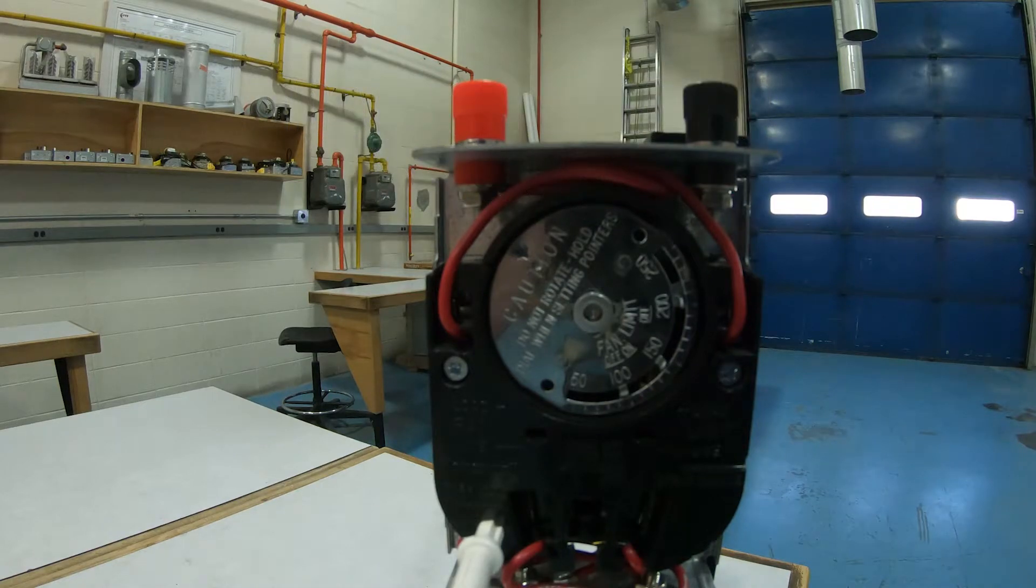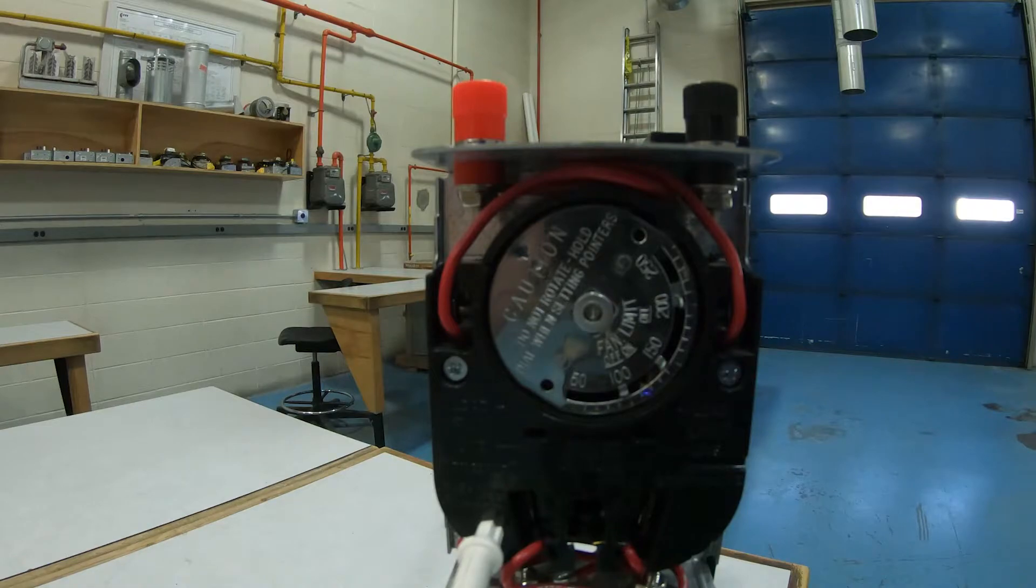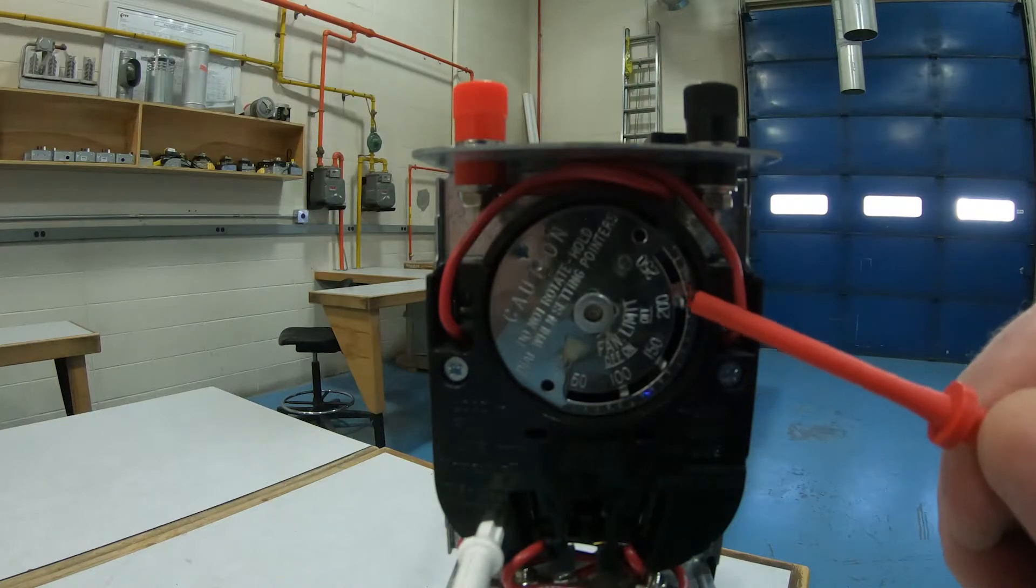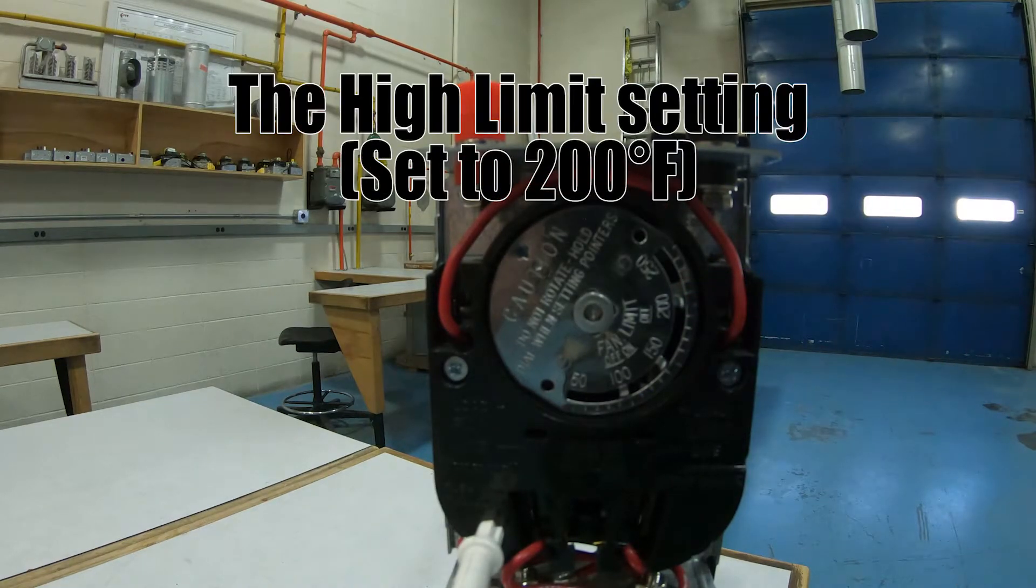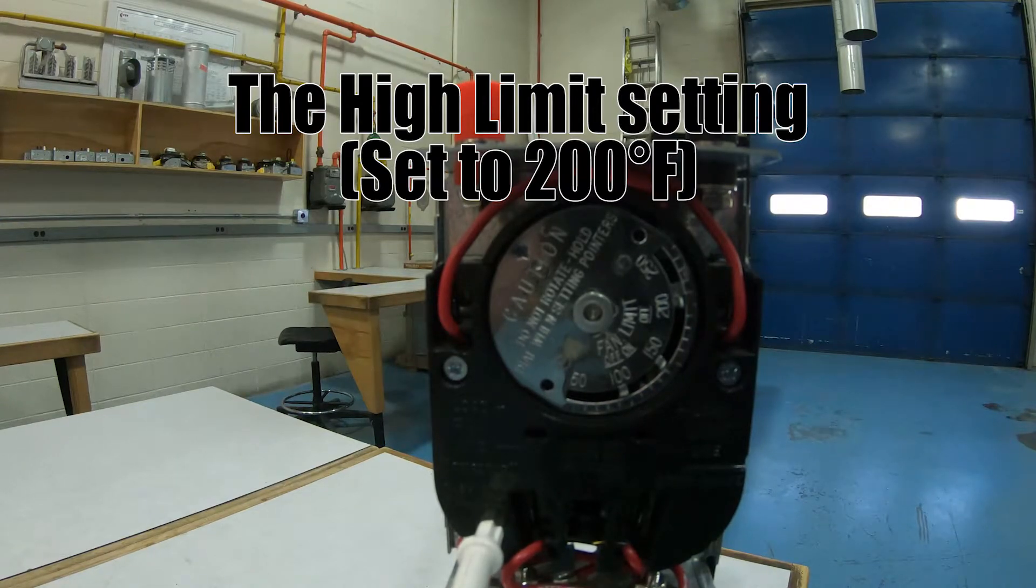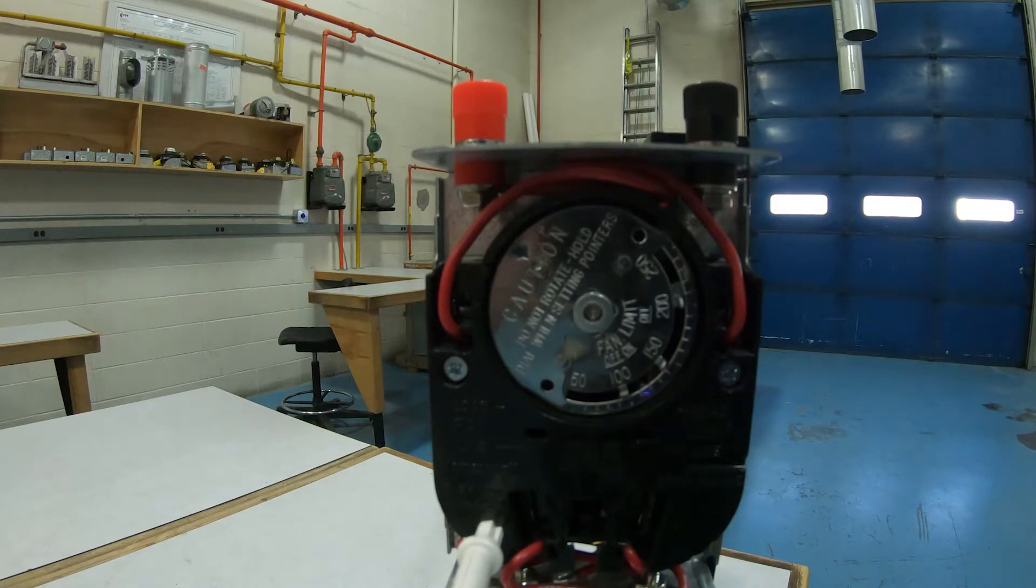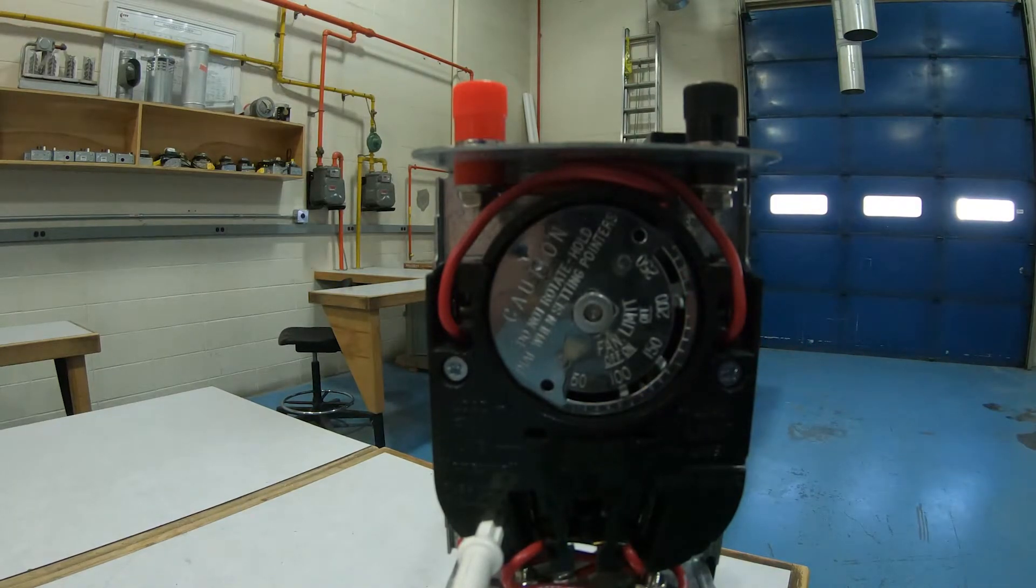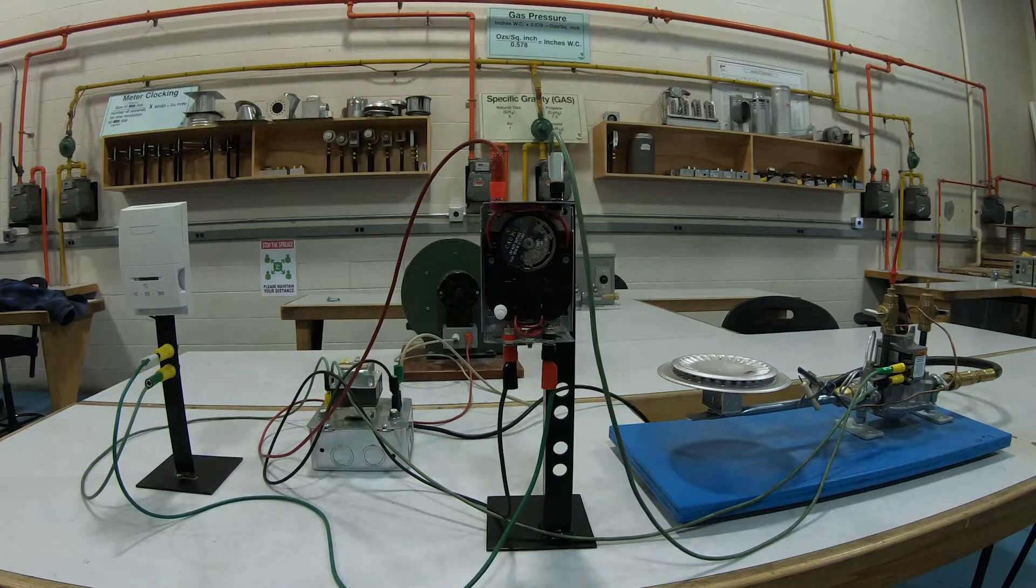If however we have a problem, like the blower motor is not working properly or a plugged filter, when we're heating up we'll get up to my high limit setting, which in this case is 200 degrees Fahrenheit. Main burner shuts off and the fan, if it's working, continues to run to cool down the heat exchanger. And when this gets low enough in its temperature, the burner will kick back on again.